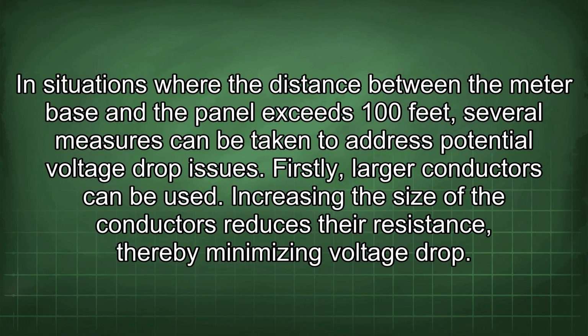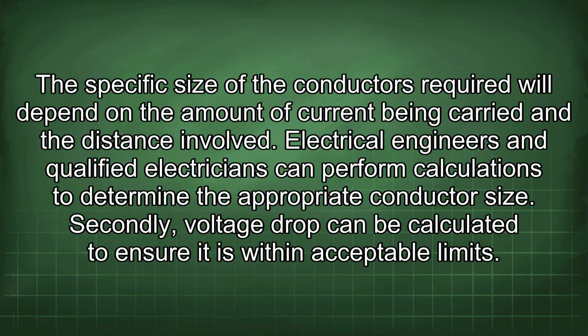Firstly, larger conductors can be used. Increasing the size of the conductors reduces their resistance, thereby minimizing voltage drop. The specific size of the conductors required will depend on the amount of current being carried and the distance involved. Electrical engineers and qualified electricians can perform calculations to determine the appropriate conductor size.